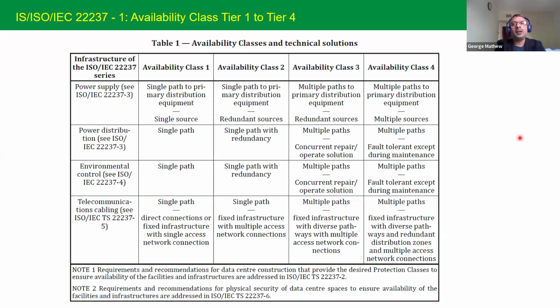So it comes to a total of 500, where for these 500 the equipment number is n. For example, we have 500, which is 100 into 5, so the n is 5. In tier 2 or class 2, the UPS in this particular case will be 6 numbers, so 500 is n plus 1, which will become 6 UPSs into 100 kilowatt. Or if we select 250, it becomes 2 UPS for the load and 1 for the standby. So 250 plus 250 plus 250, or 250 into 3 numbers, which is called n plus 1.